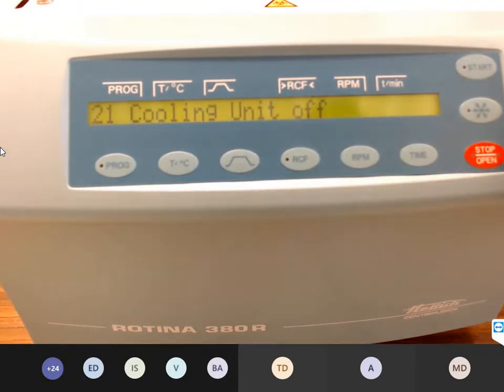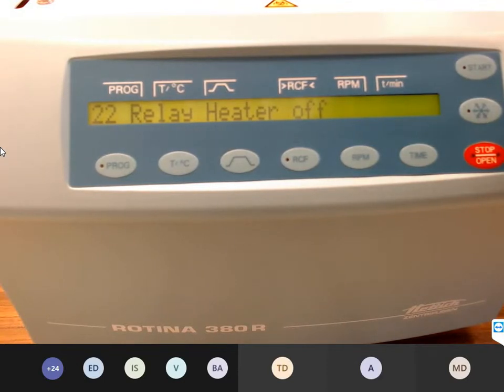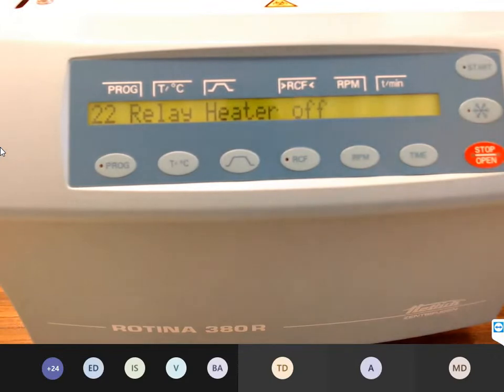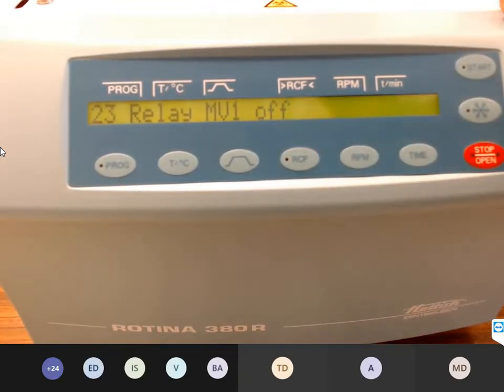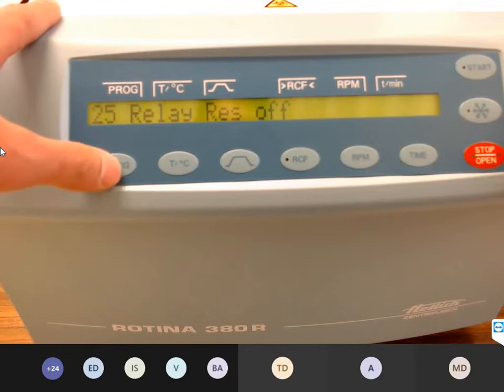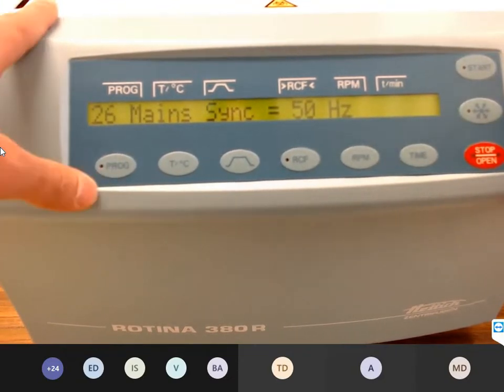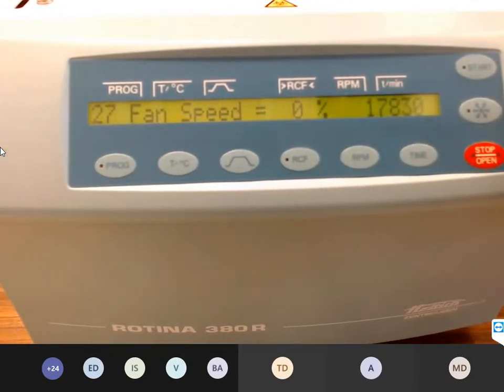Cooling unit. Switch on, switch off the compressor. It works. The heater relay. You can hear the click. The relay is working. This is the relay of the fan. You can hear the click, and the fan works. Okay. The second relay, the reserve relay, the mains earth. And you can also check the fan of the condenser.